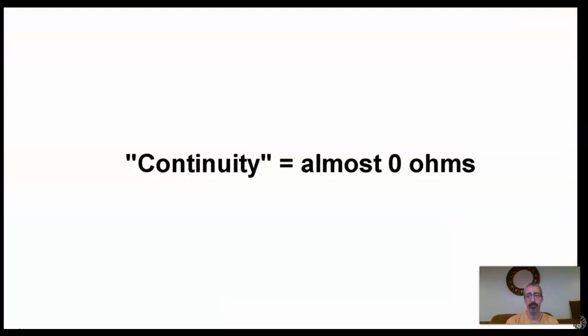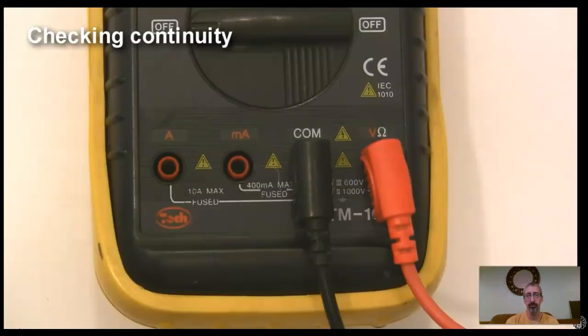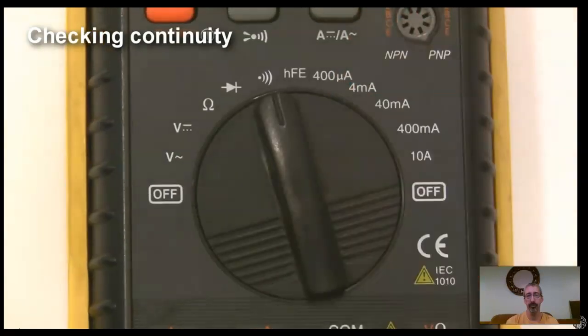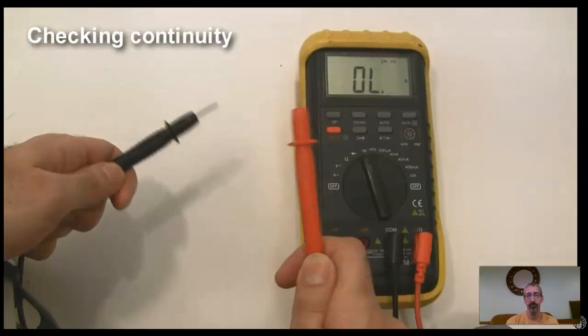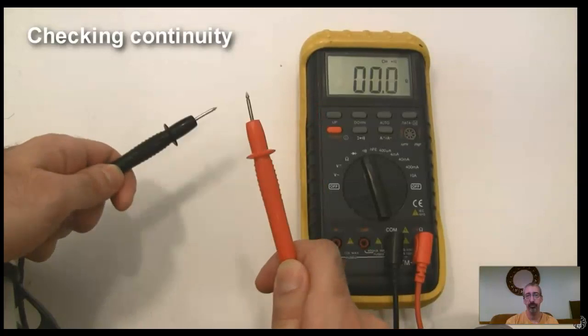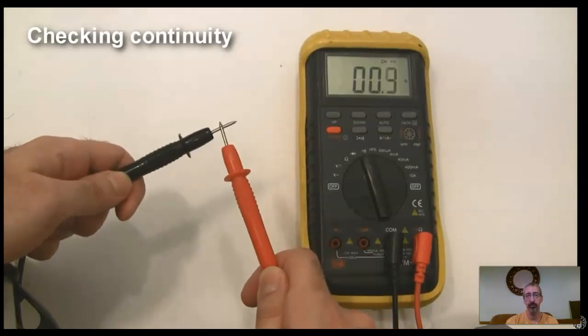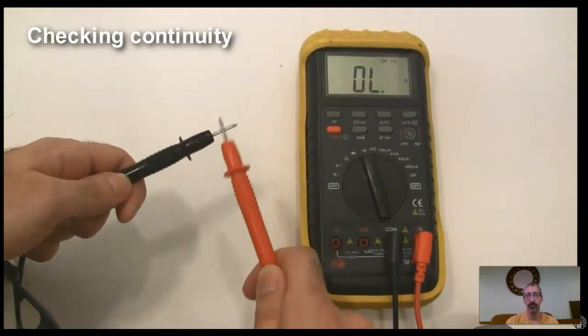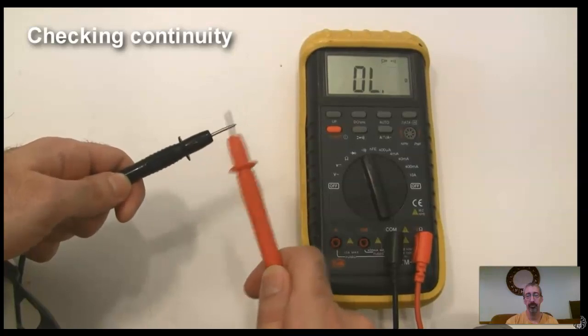Next, let's talk about continuity. Measuring continuity basically just means checking whether or not there's a good connection between any two points in a circuit. To measure continuity, make sure your red probe is in the jack labeled continuity, or in my case resistance, and set the dial to the continuity setting. Test that the continuity function is working correctly by touching the probes together. Whenever there's almost zero resistance between two points, the multimeter will beep.